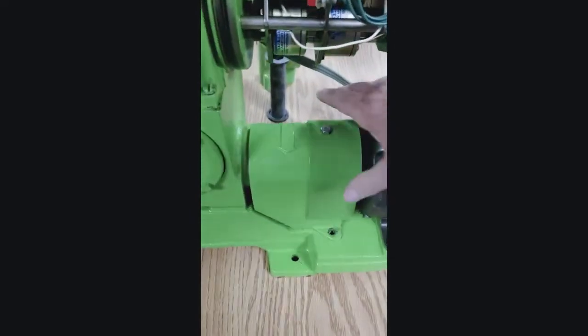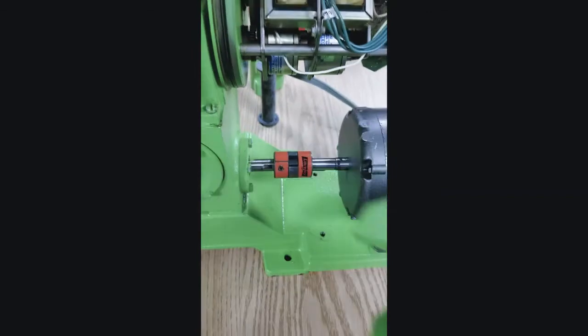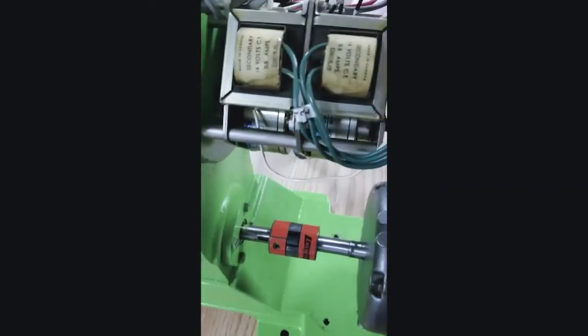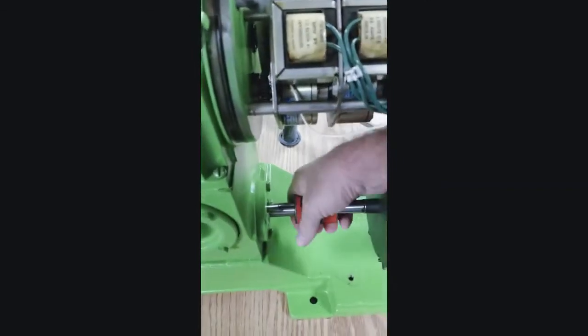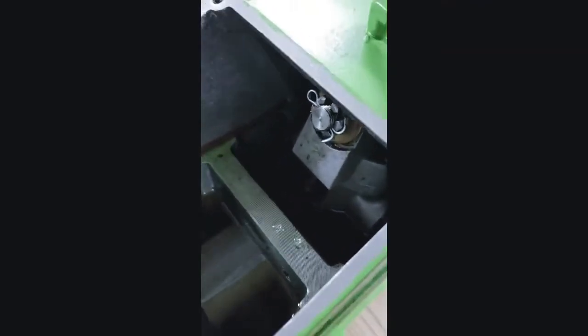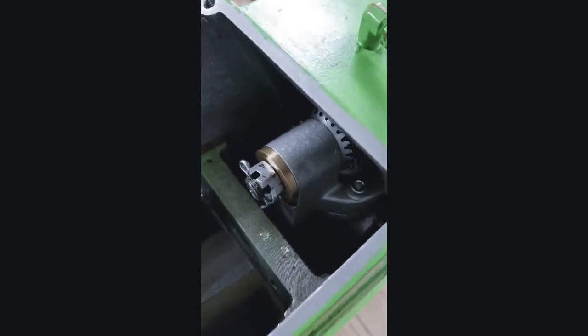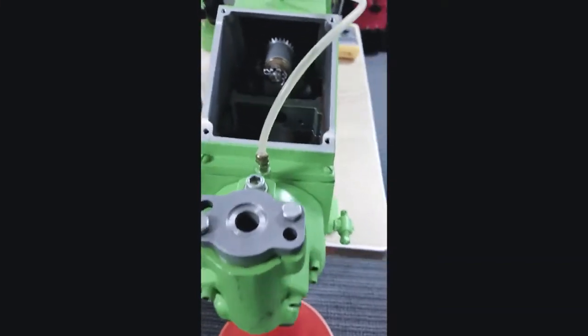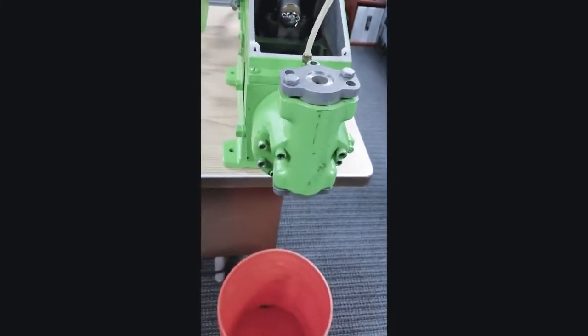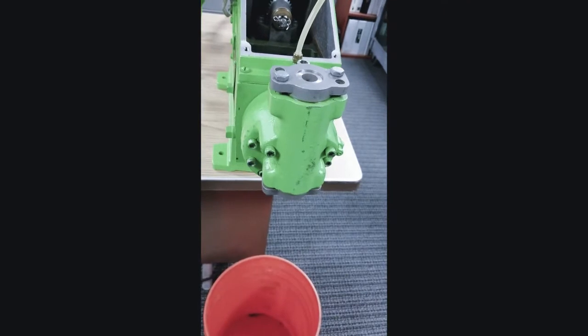With that done, the first step will be to remove your coupling guard and rotate the coupling manually until you can verify that the piston is in the fully rearward position. So I want to bring the top of the housing all the way forward, and we're set. Now we are ready to drain the head and remove it to replace the Hydratube.